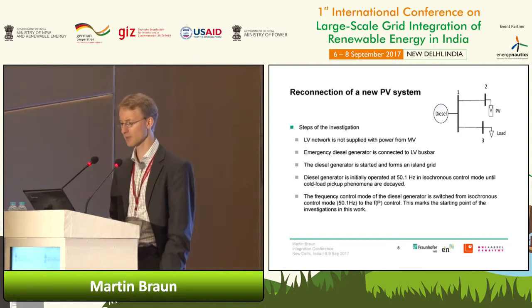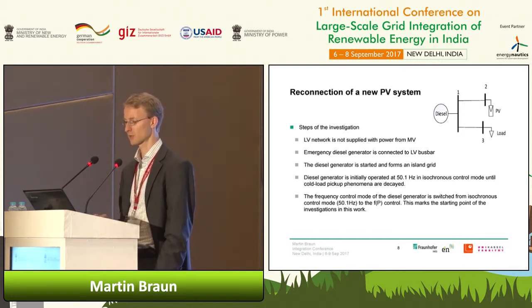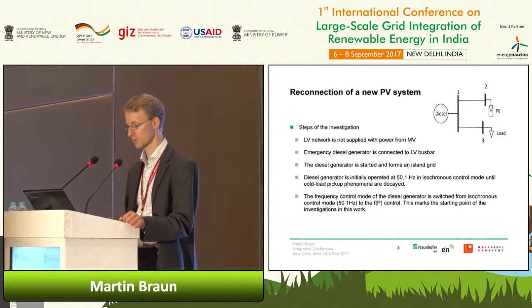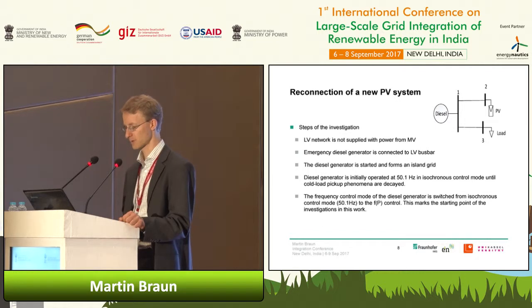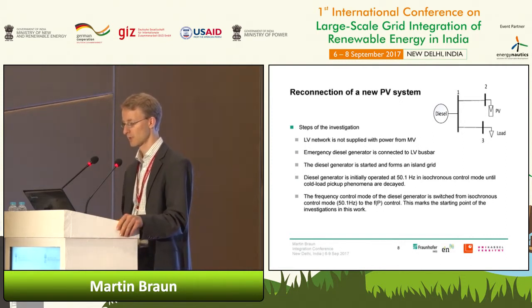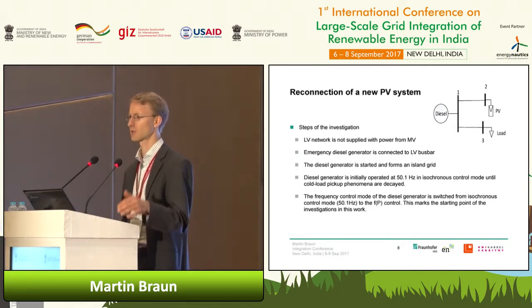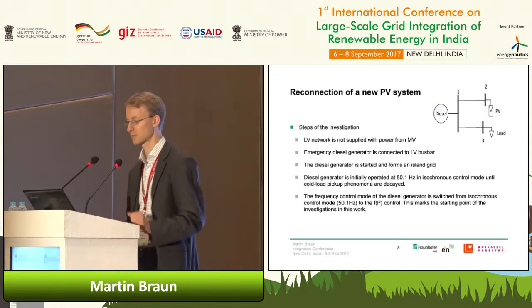So what we see is that we first assume the low voltage network is not supplied with power from the medium voltage. Then an emergency diesel genset is connected to the low voltage bus bar. The diesel genset is started and forms an island grid, and it is initially operated at 50.1 Hertz. That's an isochronous control mode that allows to sustain the cold load pickup phenomena. If you remember the values I gave before, at 50.1 Hertz the PV systems will not connect, because they will only reconnect if the frequency is below 50.05 Hertz. So the PV systems are not active in this isochronous high over-frequency mode.